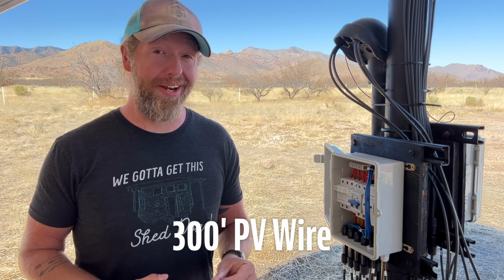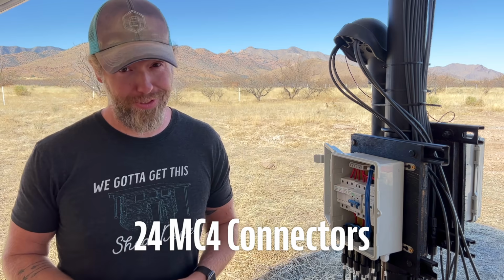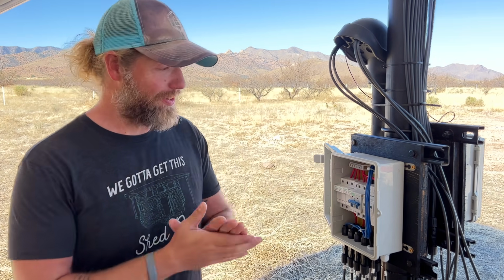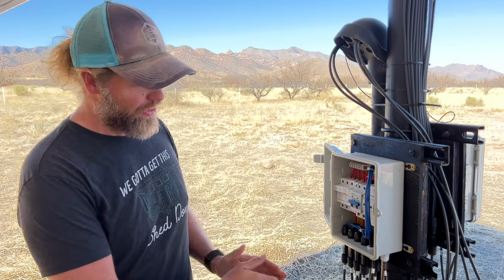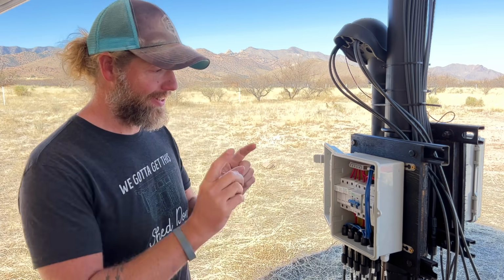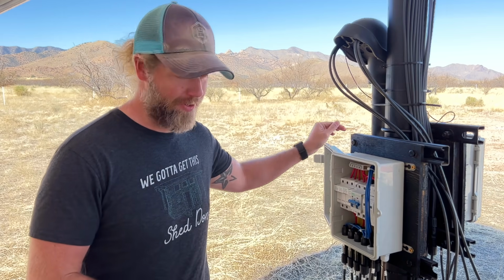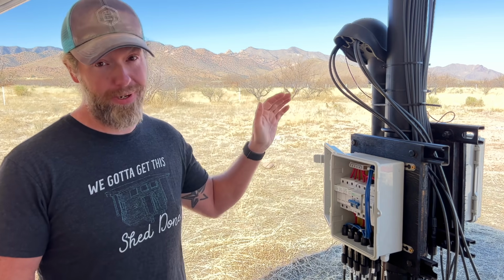In order to get all of our wires into our combiner box, we had to buy 300 feet of solar wire and 24 MC4 connectors. With each series of 5 panels, we needed to connect in parallel, and so that's what this combiner box does. You can see this one has 4 inputs, so we have 4 of our 5 panel arrays on this one and then 2 on the other one. And also that means that we have room to expand on that other box if we ever want to add more panels.